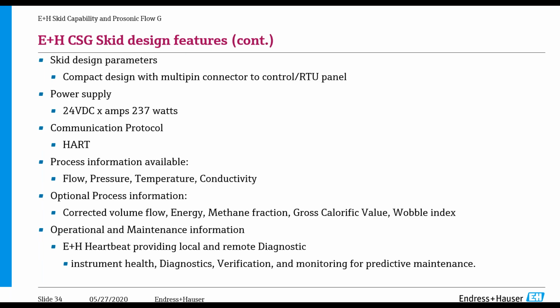All right, just continuing on some of the features. So, a compact design with multipin connector. As I mentioned before, this is a turnkey solution if it's purchased together with the Rockwell control system. The way that we connect the skid to the control system is with a multi-pin connector, and we take that multi-pin connector into the non-hazardous area. What that does is allow us to control the cost. If you're doing switching or connections inside a hazardous area, immediately the cost goes up.